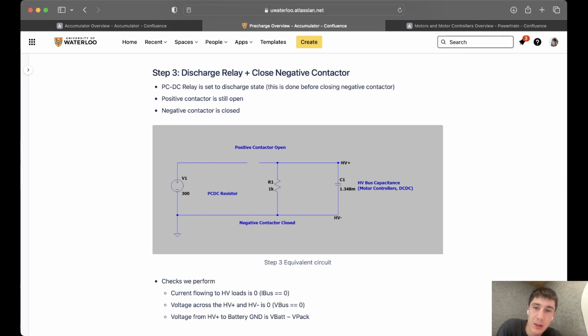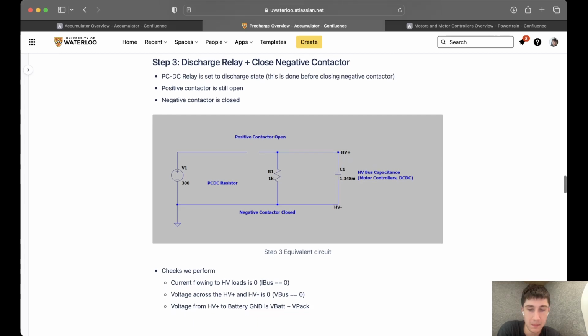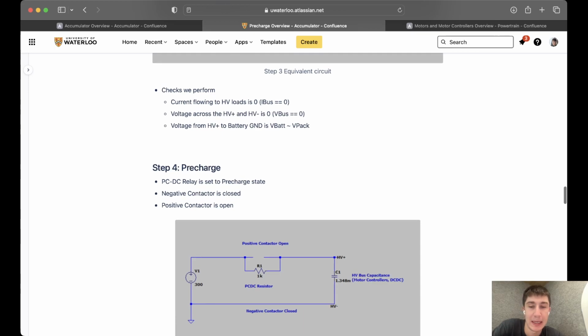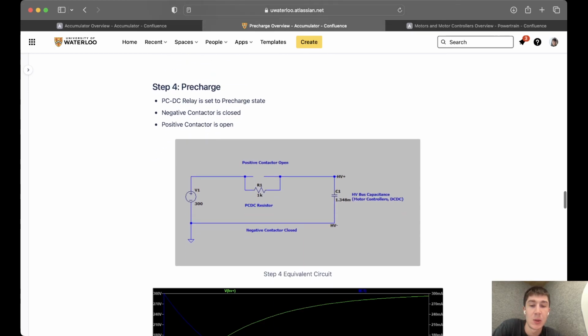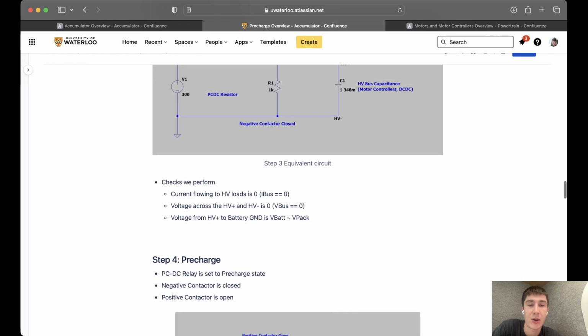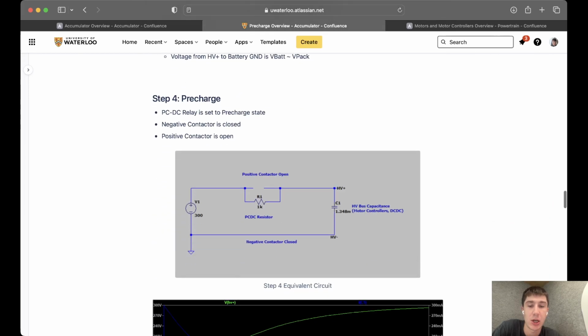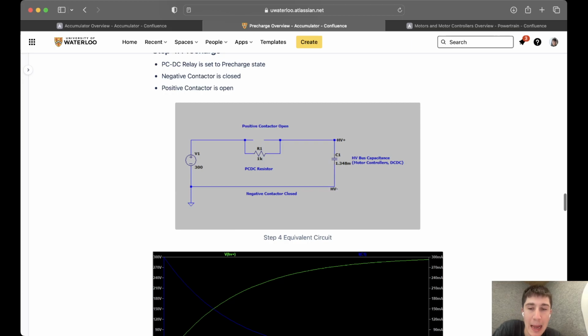Step 3, we put the resistor back in discharge mode, so it's across our high voltage load, and we close our negative contactor. Still, nothing is occurring. We're just performing checks. No current can flow here. Our final step is to begin precharge. So we move our resistor from across our high voltage load to across our positive contactor. And you can see here now we have a path from our high voltage battery through to our high voltage load. There's a solid current path.